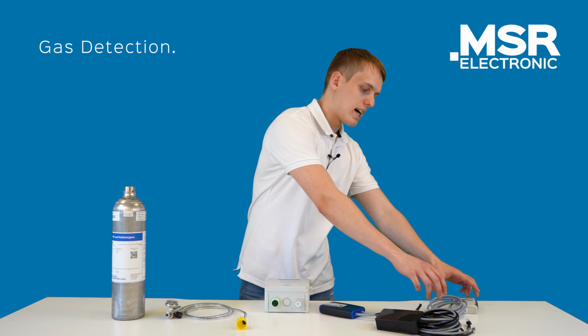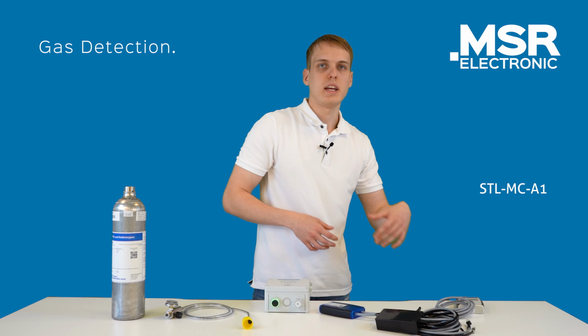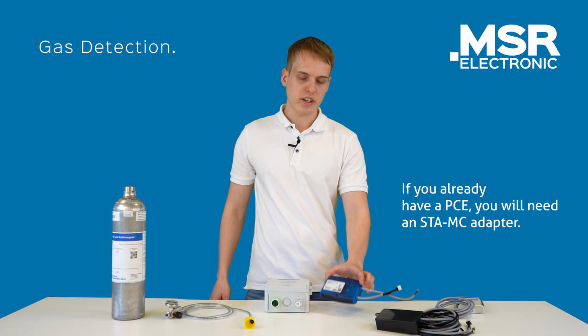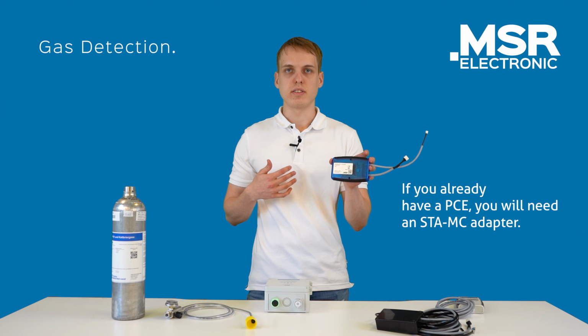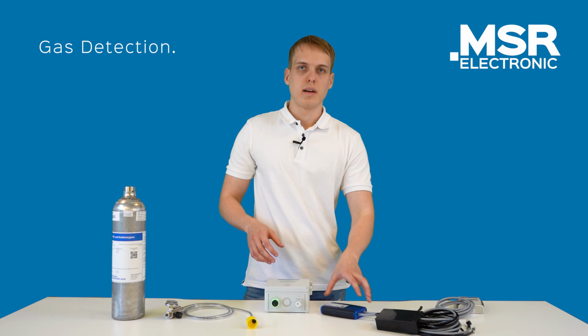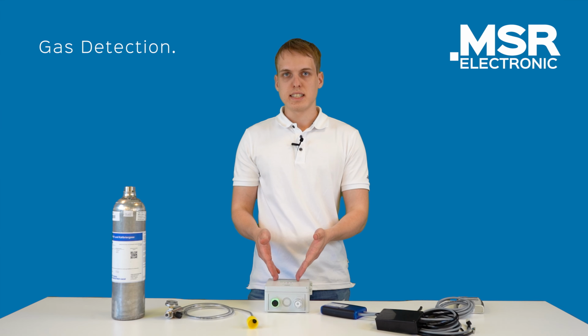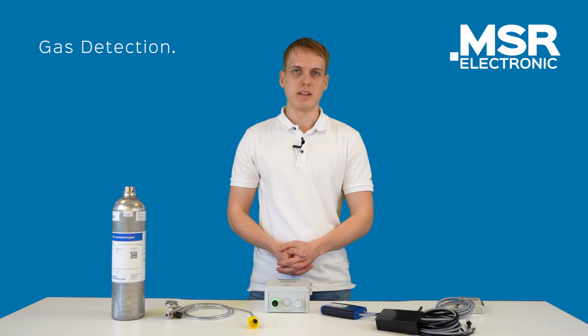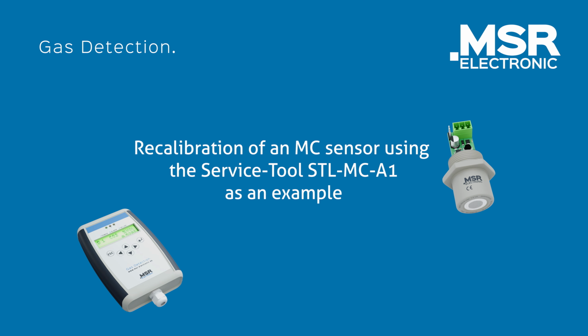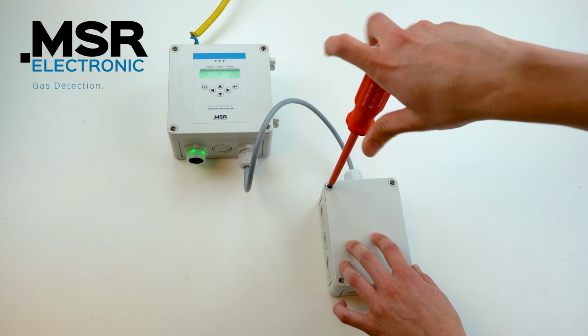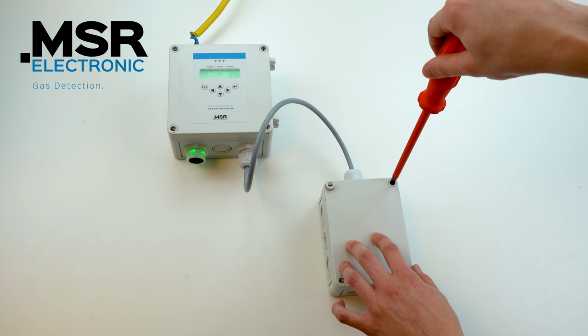To perform the calibration, you will need either a STL06MC2 or, if you already own a PCE06, then you will need the converter box, our STA06MC2, because with the integrated display of the device, the calibration of the analog sensors is not possible. We open the device by loosening all 4 screws and carefully lifting off the cover.